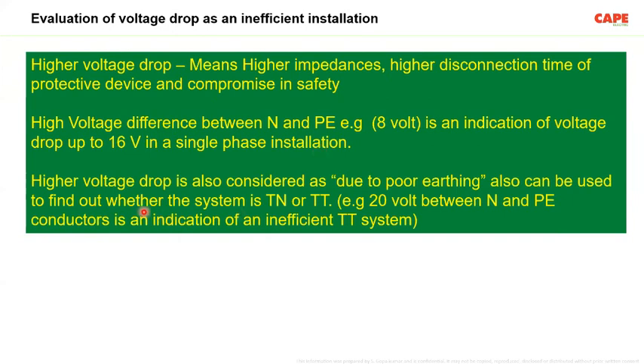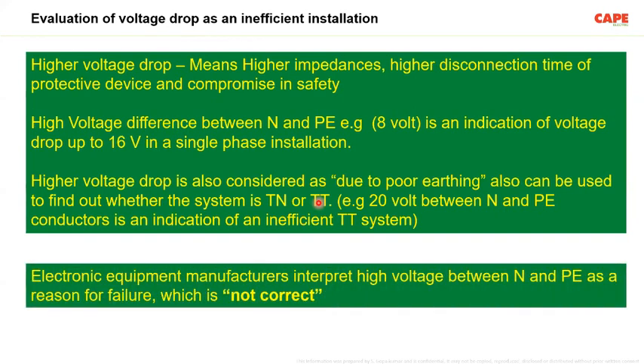Now, a higher voltage difference is also considered to be due to poor earthing. This technique also can be used to find out whether the system is TT or TN. Most often, in the case of a TT system with a very unreliable earth electrode or loose contacts, sometimes the protective conductor to neutral voltage is either unstable or very high. Of course, we are not supposed to follow the TT system. As per our regulation, we are supposed to follow the TN system. So what I wanted to tell you is that voltage drop is also a very good way of finding out the probable causes of problems in the future.